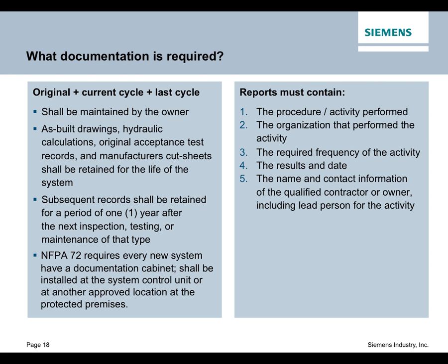NFPA 72 actually goes one step further for a fire alarm system and requires that a documentation cabinet be installed near the system control panel or at another approved location in the protected premises. So it's an actual red box that's labeled fire alarm documentation, and in there resides the as-built drawings, the software program, and you know what's happening today? Many times it's a flash drive that contains all this information electronically.